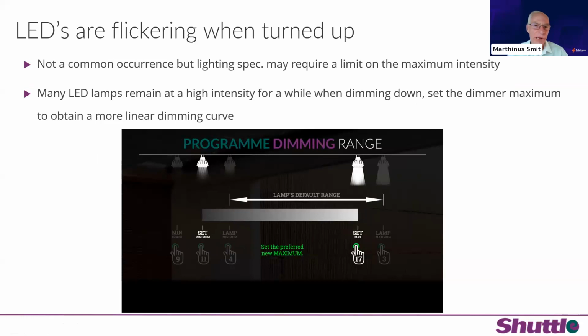But it's very rare. But there may be a requirement from your lighting specification that your maximum intensity must be limited, or even, for example, in a baby's room. And then the other problem that you sometimes find, as we mentioned earlier, is a non-linear dimming characteristic of some of the LEDs. We find that as you turn the dimmer down from maximum, the light essentially stays exactly the same, and then at a stage it starts dimming down. So in all these cases, you can actually set your maximum intensity to avoid these conditions.